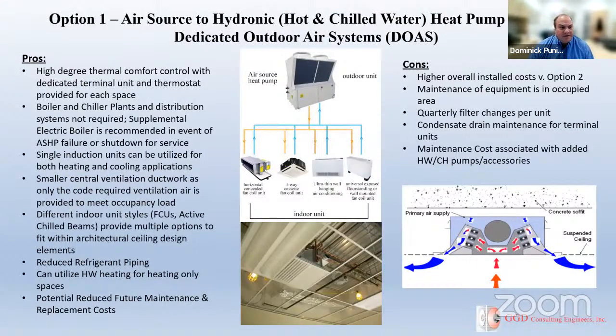So option 1, this would be an air source to hydronic hot and chilled water heat pump plant. So there would be an outdoor air source chiller/heater that generates hot water and chilled water that would be distributed to your air handling systems and fan coil units or chilled beams to maintain the space heating and cooling requirements. Air handling units would largely be used for ventilation purposes, and then your additional heating and cooling that would be needed would be served by terminal hot water, chilled water equipment.